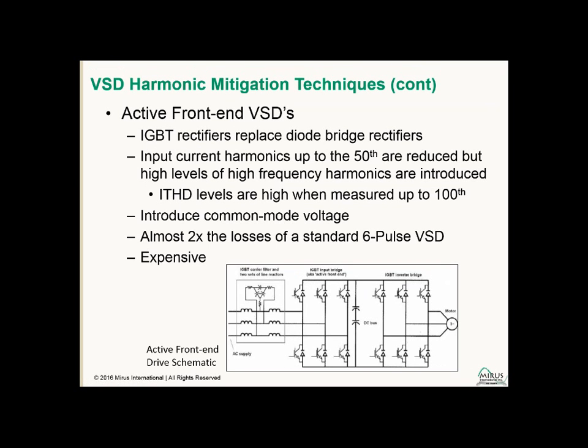There are a lot of active front-end drives out there right now that people are offering for harmonic mitigation. These will have IGBT rectifiers on the front end instead of a simple diode bridge. These can reduce the current harmonics in the lower frequency range, so say up to the 50th harmonic. But they will introduce a band of high frequency harmonics above the 50th, typically in the 50th to the 100th, which is related to the switching frequency of the IGBTs. So if you have IGBTs switching at, say, 4 kilohertz, 4,000 hertz divided by 60 is going to be about the 67th harmonic. So you're going to see a band of harmonics out at the 67th.